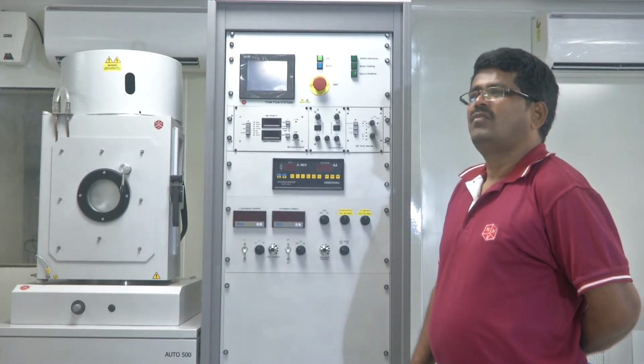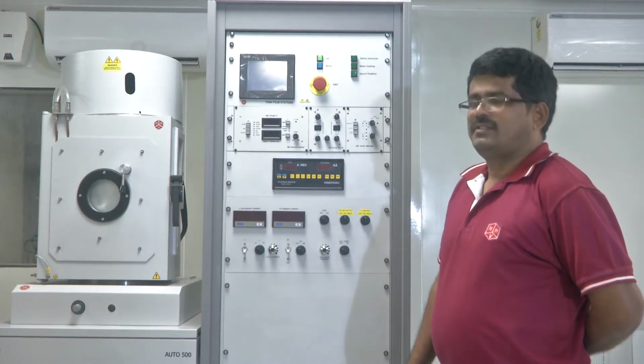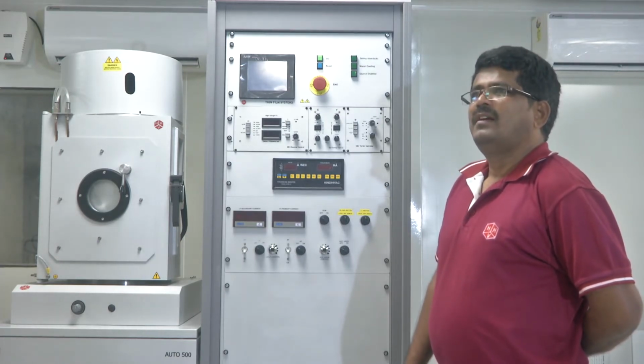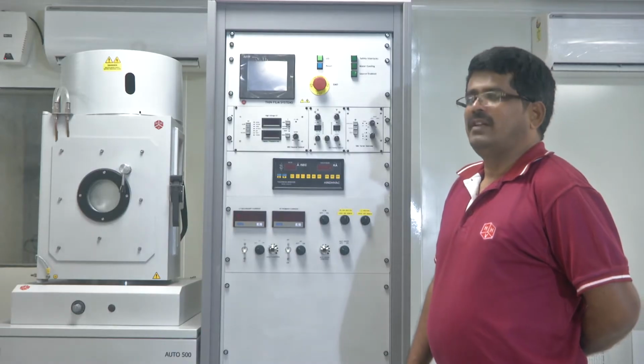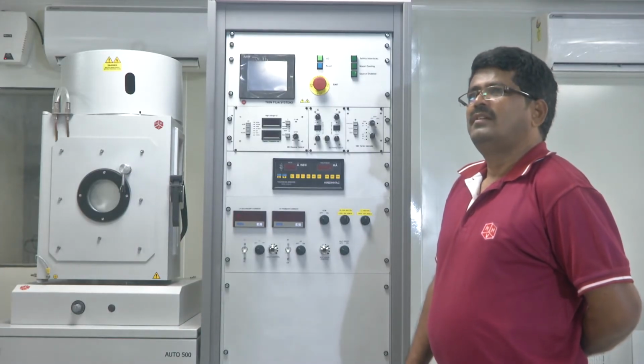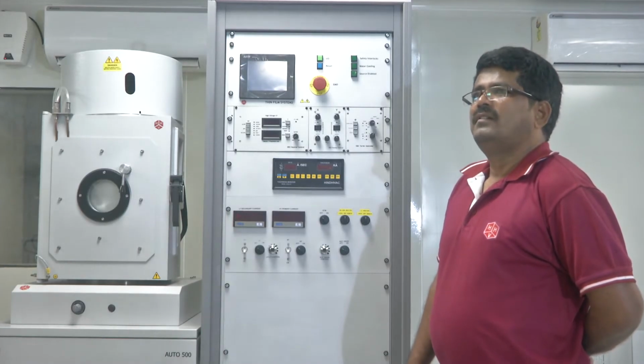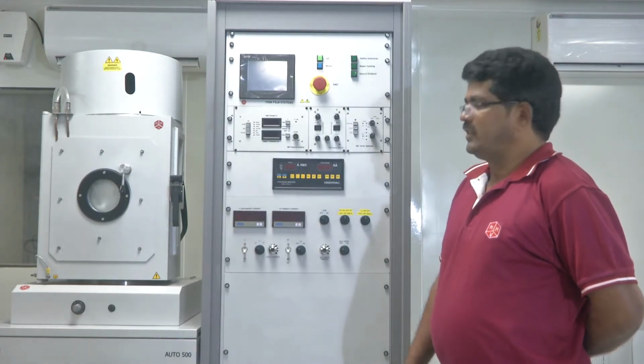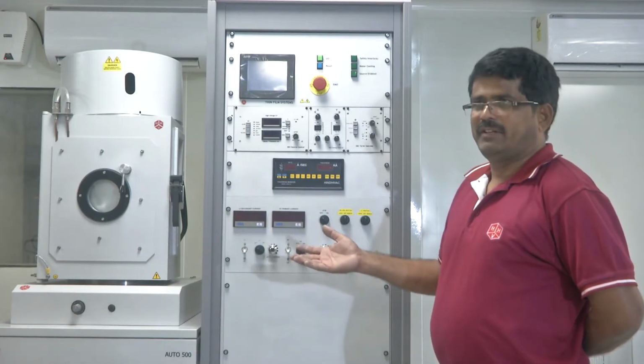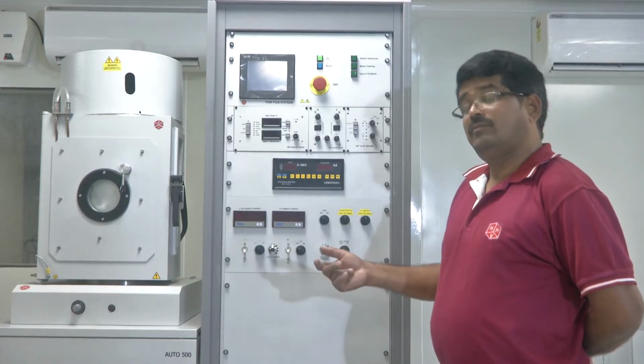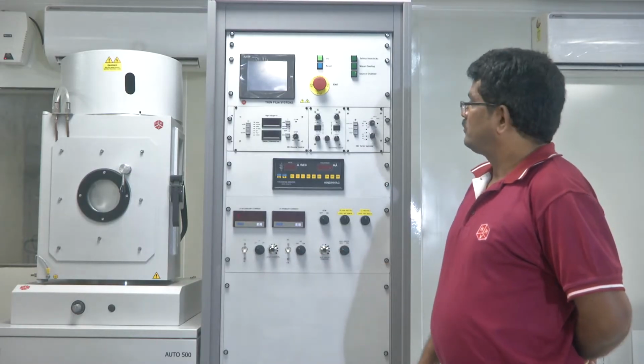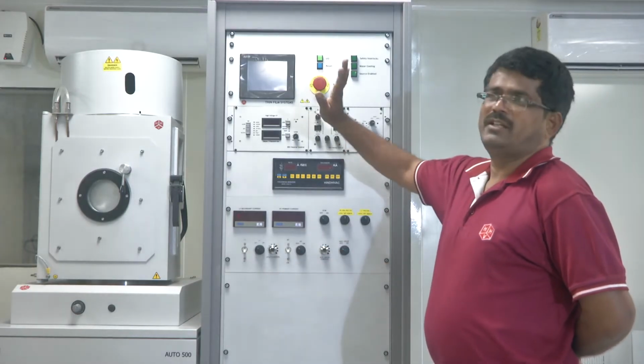First the roughing pump will come on. Then we go to the TMP. Once the roughing pump is done, the high vacuum valve will open, then the turbomolecular pump comes in. Once it reaches sufficient pressure, we can start the process. We have an instruction manual, which will be given. Each switch is manual, through a touch screen.